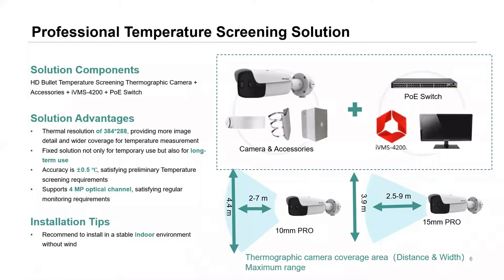We have three ranges: the professional range, eco range, and a handheld range. The professional range is offered in a bullet-style camera. Setup is straightforward — plug it into a PoE switch on the network, download the iVMS-4200 software, and you can witness real-time alarms sent to iVMS-4200 from the camera, as well as temperature readings overlaid on the stream itself.